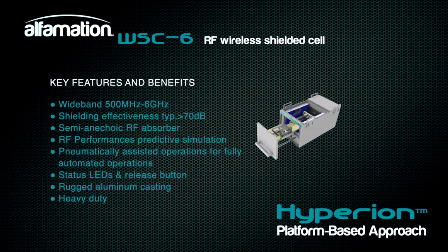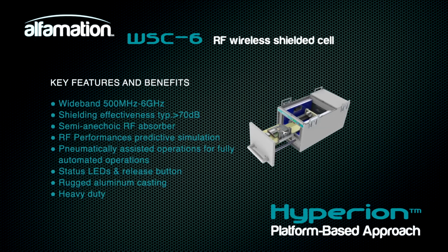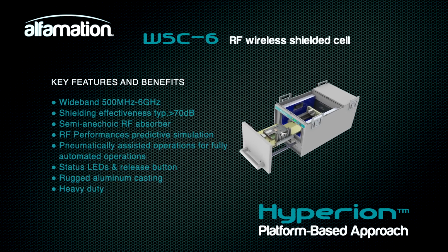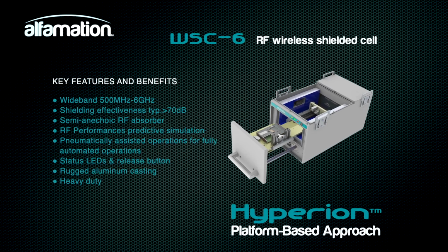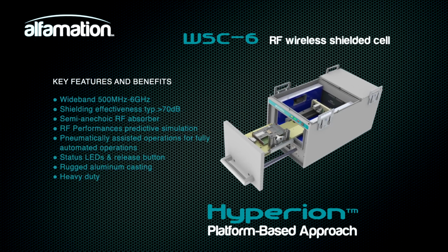Standard shielded semi-anechoic cell for wireless devices prevents interference with external environment among devices under test yet simulating an open field. Over-the-air antennas require coupling and positioning characterization to meet best efficiency within the cell, where hybrid RF absorbers have been positioned after a careful design.